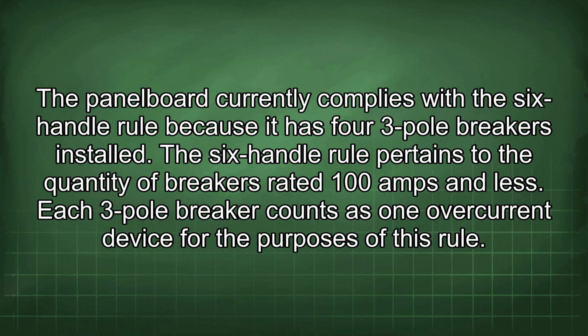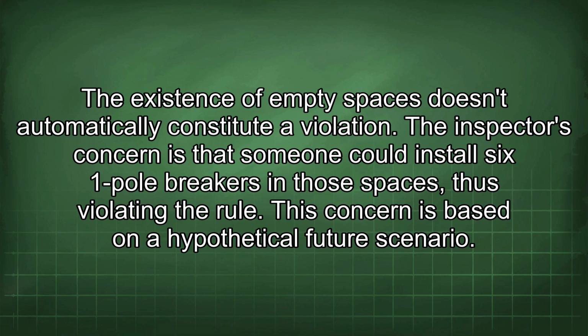The panel board currently complies with the six-handle rule because it has 4 3-pole breakers installed. The six-handle rule pertains to the quantity of breakers rated 100 amps and less. Each 3-pole breaker counts as one overcurrent device for the purposes of this rule. The existence of empty spaces doesn't automatically constitute a violation. The inspector's concern is that someone could install 6 one-pole breakers in those spaces, thus violating the rule. This concern is based on a hypothetical future scenario.